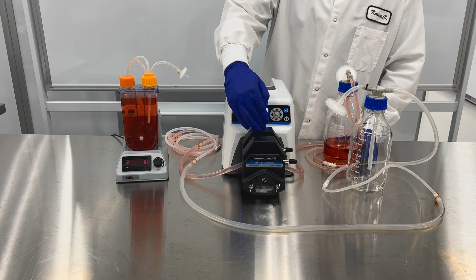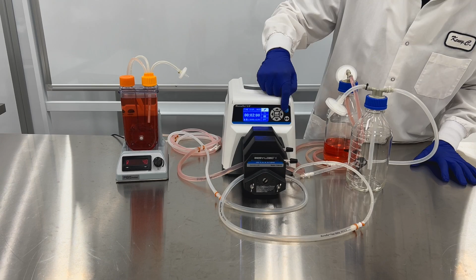Now we want to actually put our waste line into the pump head. So we can open this up. Notice this is already turned off. And you can see, because these only flow in one direction, I'm actually going to flip the orientation of this tubing. And then we'll lock that into place. So what I've done here, by flipping the orientation, that means my fresh media will be added in, while my waste media is being removed in this direction into the bottle. Now that we're all connected up, we can program our pump head to the desired flow rate and initiate the perfusion.